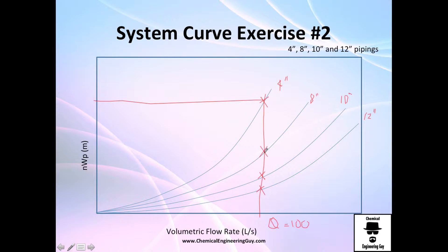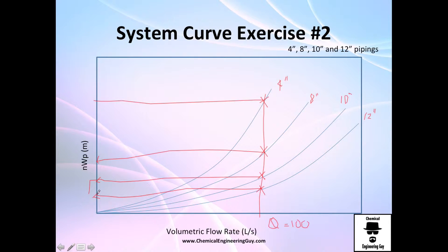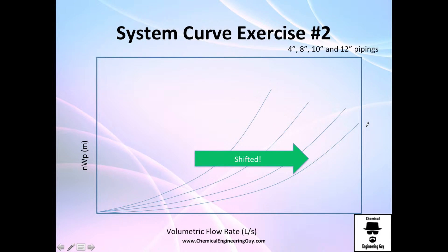For example, you will have a very high requirement for the four inch pipe, and then lower ones for larger pipes. Eventually there's almost a small change going from ten to twelve — no drastic change. But if you compare four to maybe ten inches, it's a huge change in pump requirement. This is because velocity decreases as you increase the diameter. So we shift to the right when we increase the pipe diameter, and we shift to the left when we decrease it.